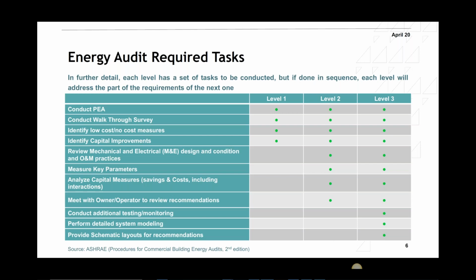So what are the energy audit required tasks? If you look at level 1, you conduct the PEA, which is basically getting the kilowatt hours per square meter per year. It would seem a very simple thing, but if it's a really big building, let's say you're doing a PEA for Dubai Mall, probably there are many different meters for electricity that you need to collect. That building is also served by district cooling, so you need to collect district cooling as well. They probably have some LPG for the kitchens and for the F&B. So you need to collect all the energy consumption and then come up with the EUI, then compare it to other similar buildings.